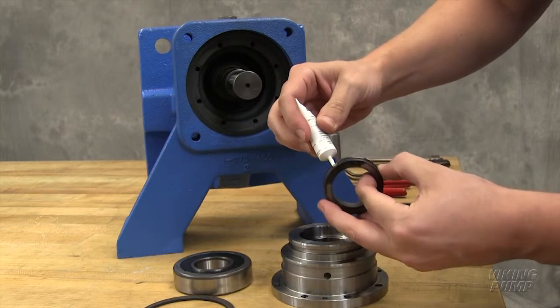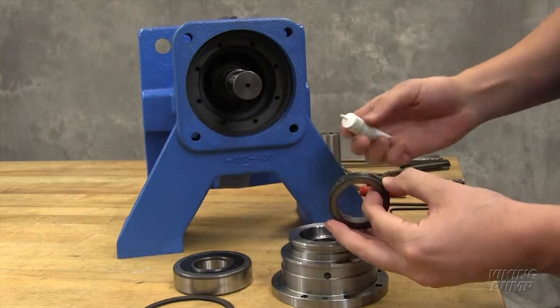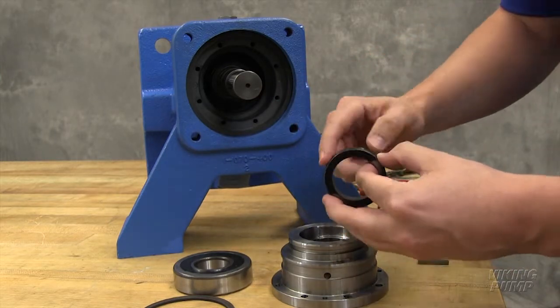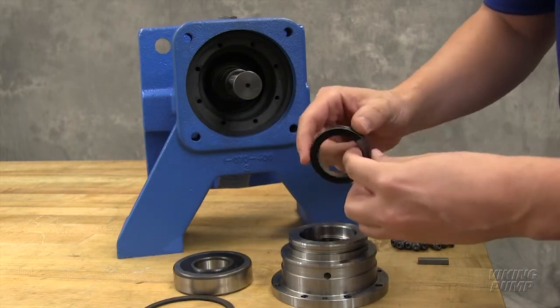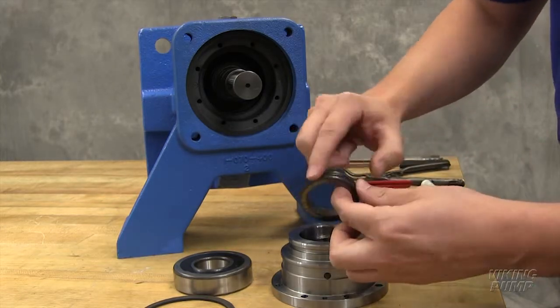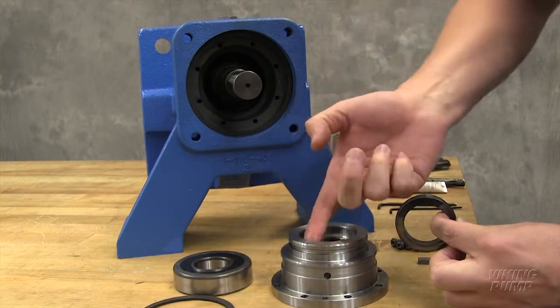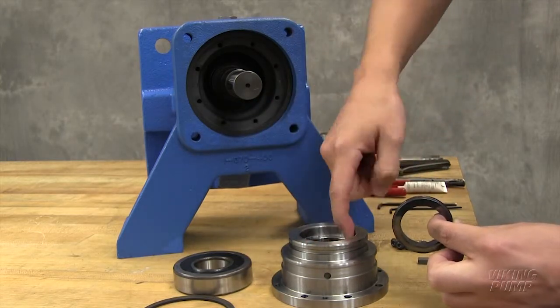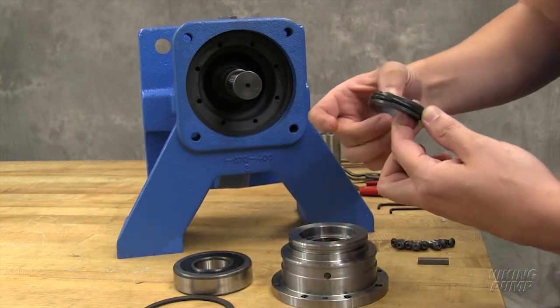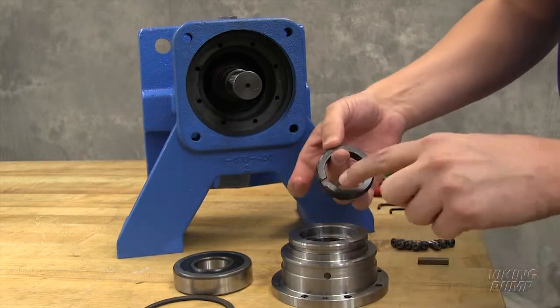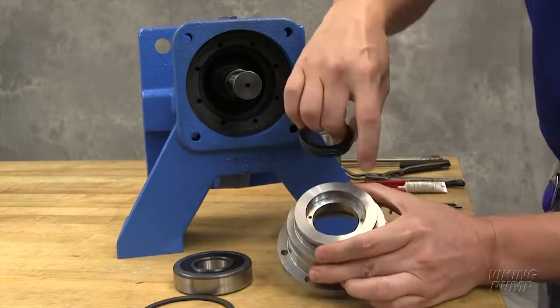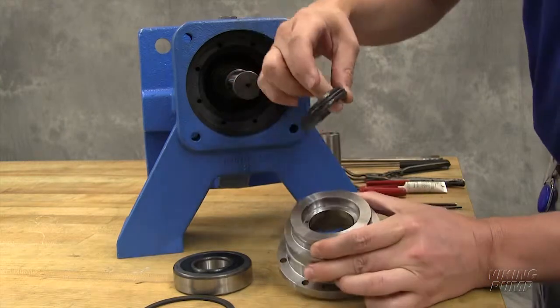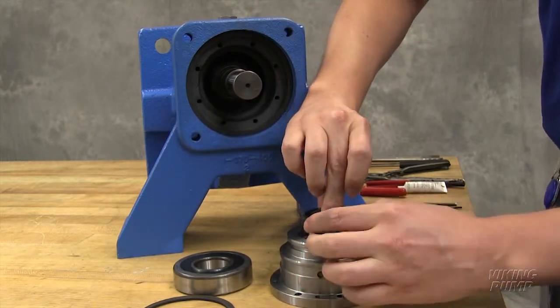To install the new silicon carbide stationary seat, first lubricate the O-ring on the stationary seat with a generous amount of light oil. Also lubricate the bore for the stationary seat. Second, align the notch in the stationary seat with the pin in the seal holder and use your thumbs or the heel of your hand to press the stationary seat into the bore of the seal holder.